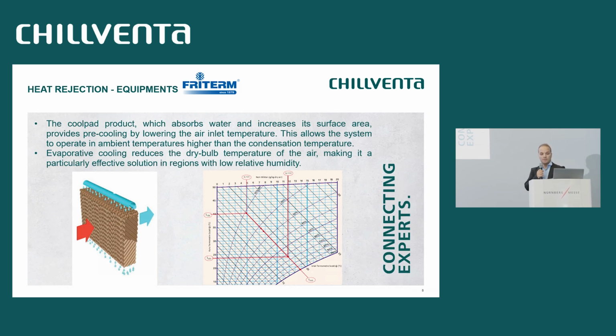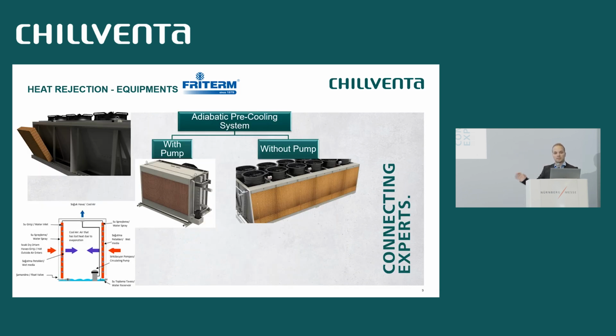Especially in the ammonia system, for better efficiency, they want to reach a 35-degree condensing temperature. So even at 40-degree ambient temperature, with this system, you can reach 35-degree condensing temperature. If we talk about the system, we have two types. One of them is with pump, the other one is without pump. In the without pump system, we send the water to the upper tray and it goes onto the pad's side, and the pads absorb some water, and the wastewater goes to the bottom tray, and it exits the system.